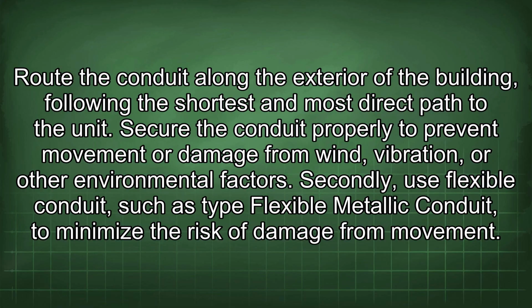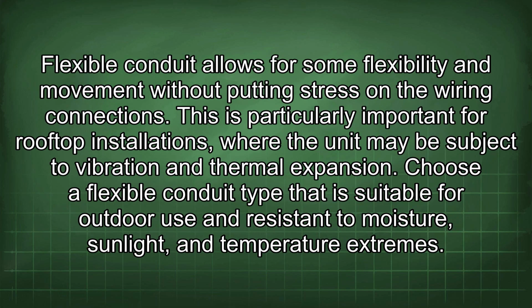Secondly, use flexible conduit, such as type flexible metallic conduit, to minimize the risk of damage from movement. Flexible conduit allows for some flexibility and movement without putting stress on the wiring connections. This is particularly important for rooftop installations where the unit may be subject to vibration and thermal expansion. Choose a flexible conduit type that is suitable for outdoor use and resistant to moisture, sunlight, and temperature extremes.